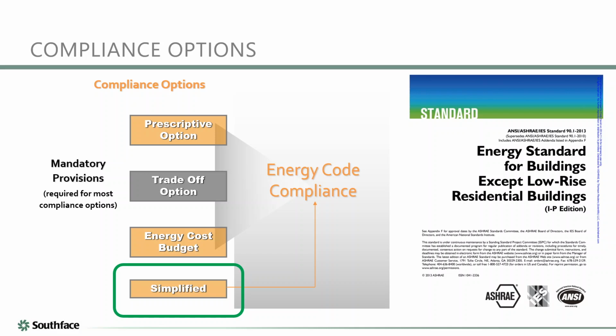And then we have the simplified pathway. The simplified mechanical pathway is only located within the ASHRAE standard. So this is not an option if you're using the IECC, and that's important to note. So if you have a building that could use the simplified approach, you're going to need to permit it under ASHRAE. If you permit it under IECC, say for your envelope and your lighting, you're not going to be able to then use the simplified pathway, which is housed in the ASHRAE 90.1 standard, for your mechanical compliance, because you're attempting essentially to go back and forth between two different versions of a code, or two different pathways within the code.